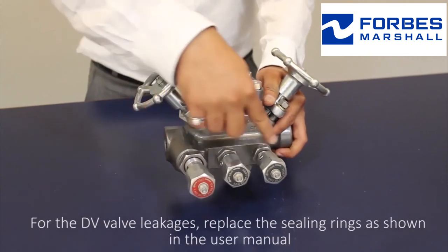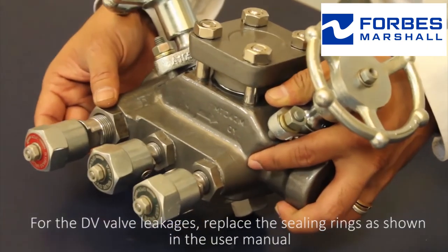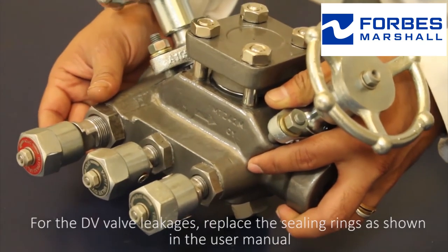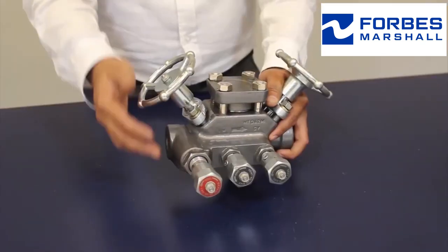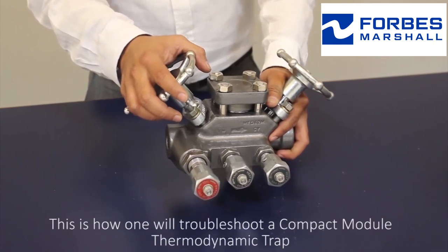For DV valve leakages, replace the sealing rings as shown in the user manual. This is how one troubleshoots a compact module thermodynamic trap.